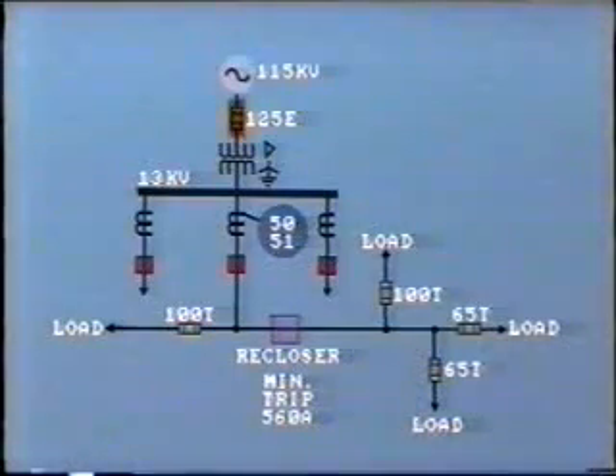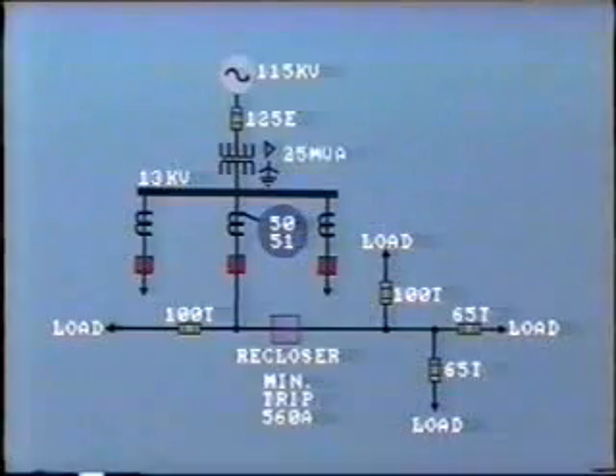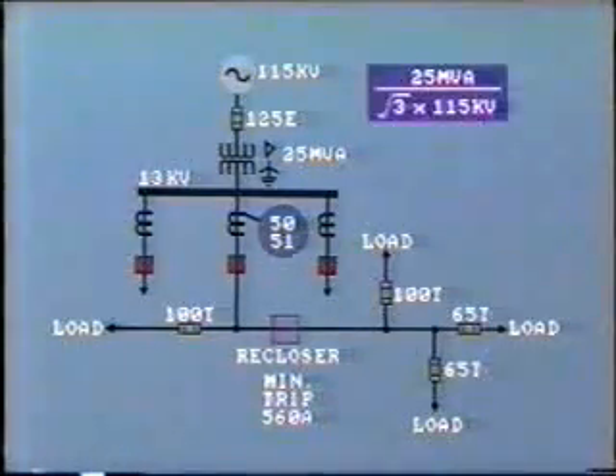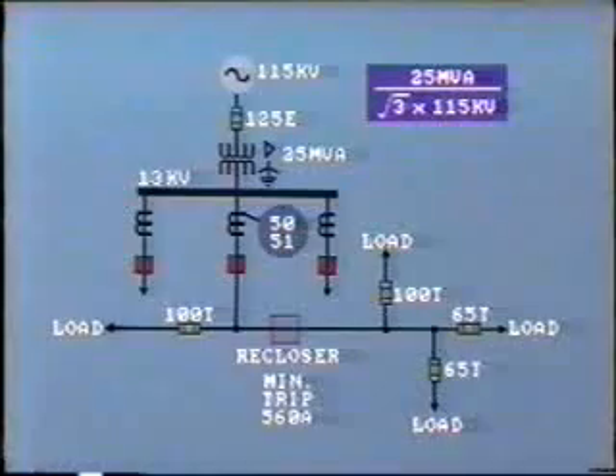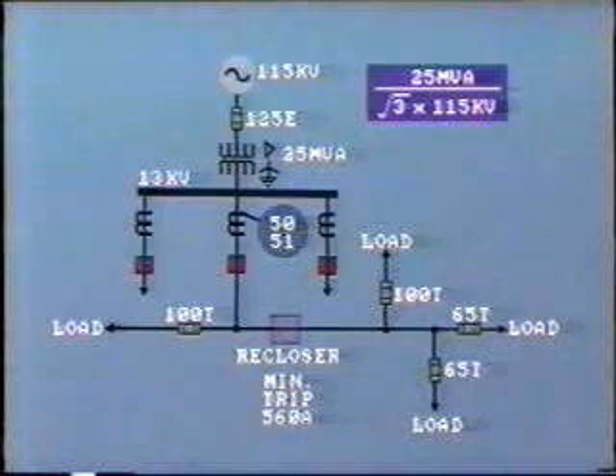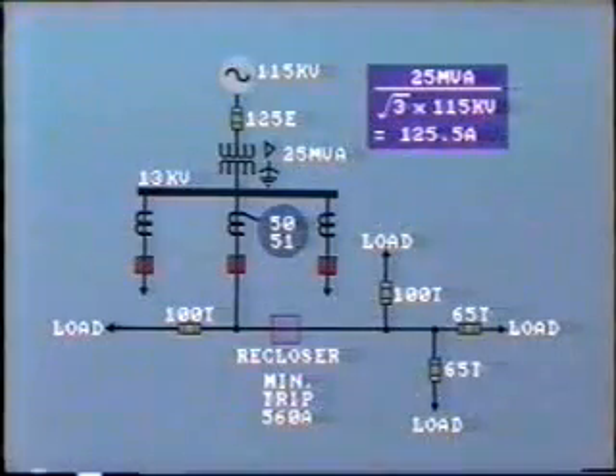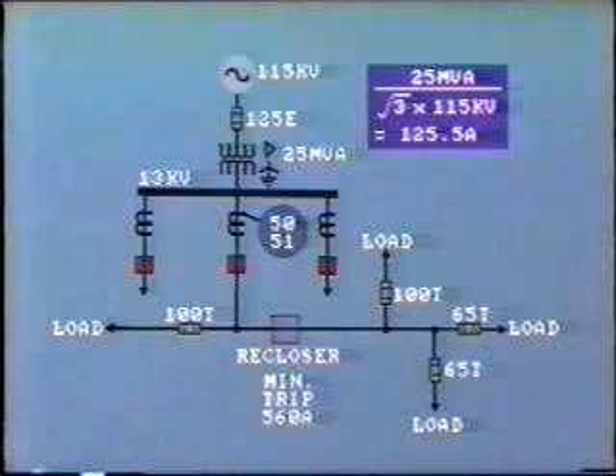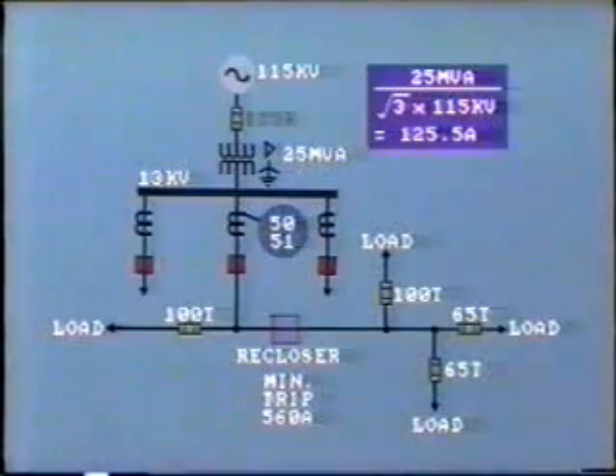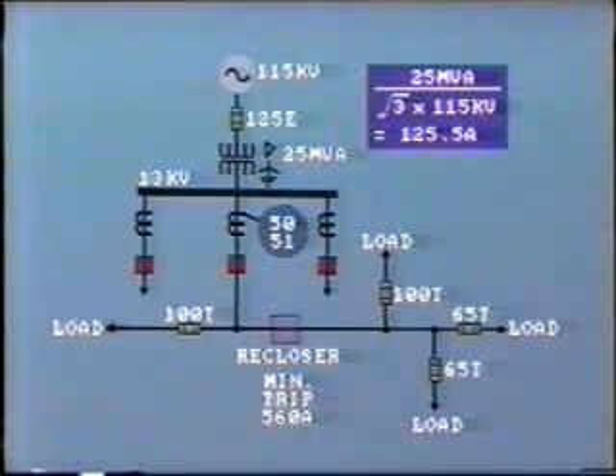The fuses on the high voltage side of the transformer. The transformer maximum capacity is 25 MVA. On the primary side of the transformer, this will result in current of 25 MVA divided by √3 times 115 kV. This is equal to 25,000 divided by √3 times 115, which equals 125.5 amps. Because of the short time overload capability of transformers, the selected fuse rating should be equal to or greater than the transformer full load rating. In this case, a fuse rating of 125 amps is installed.